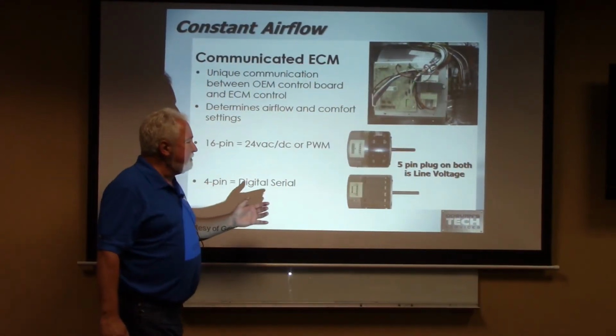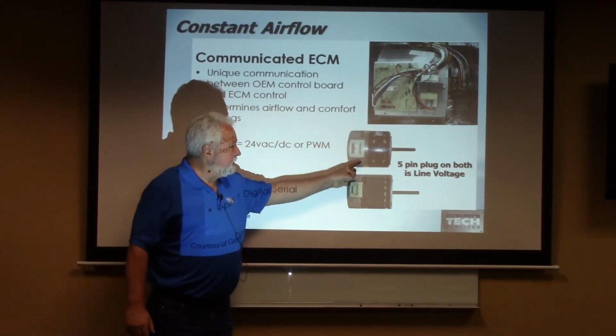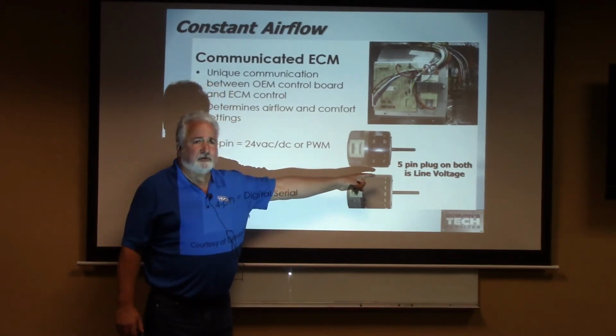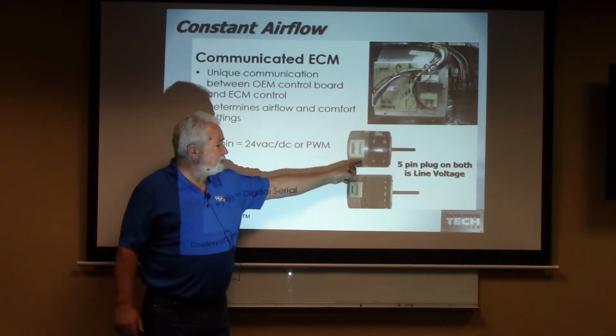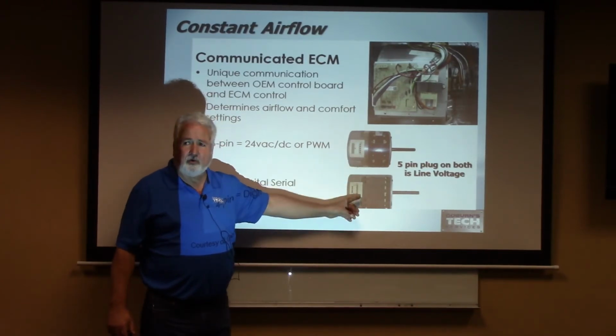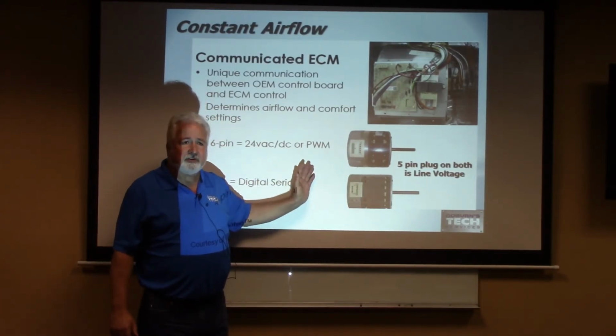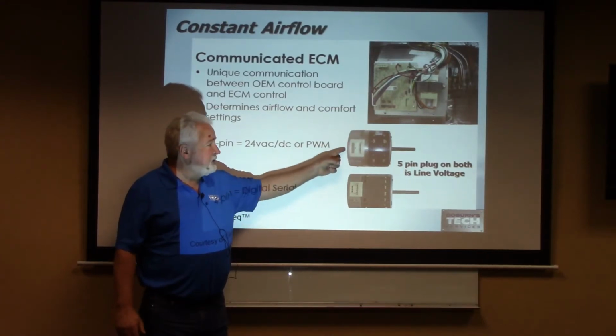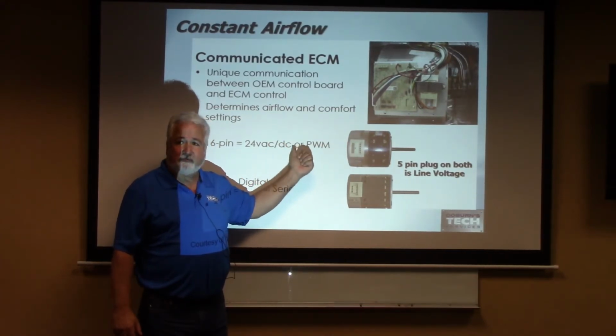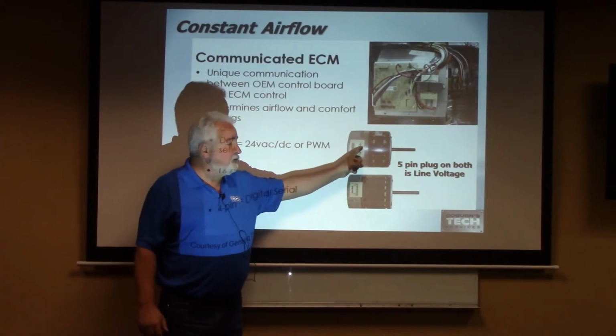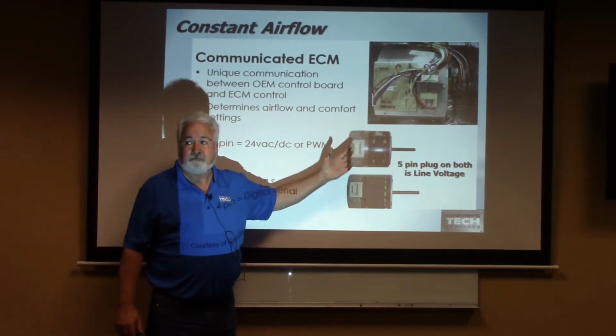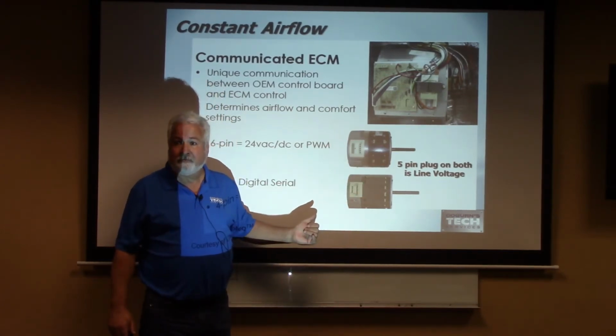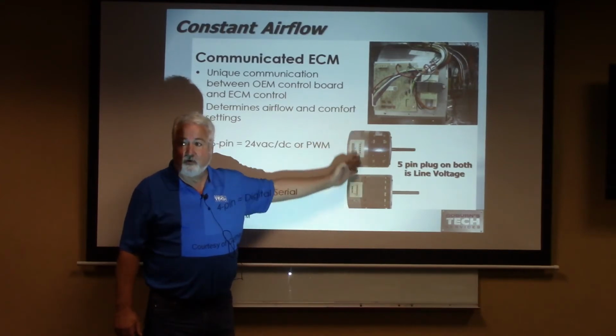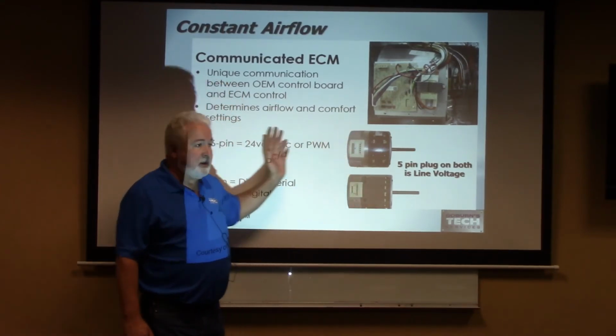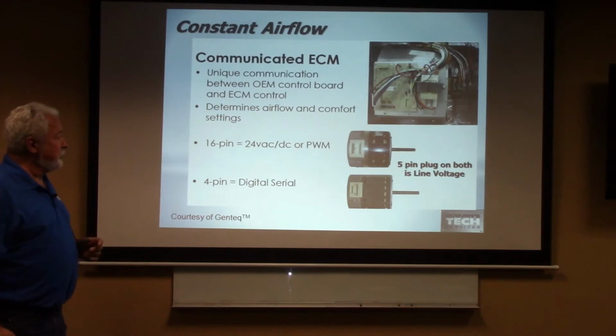You will always have the 5-pin plug on this side that's going to be your line voltage. It's either going to be 240 volts or 120 volts. That's going to always stay constant. What's going to cause it to run is going to be the communication that comes from the board. Good. So if you don't have voltage here, it's not going to run. Is that right? You first have to check, do I have voltage? If I have voltage there, then we can start working our way back to the board. Good.